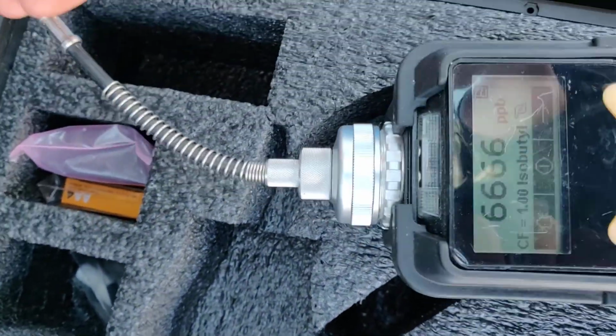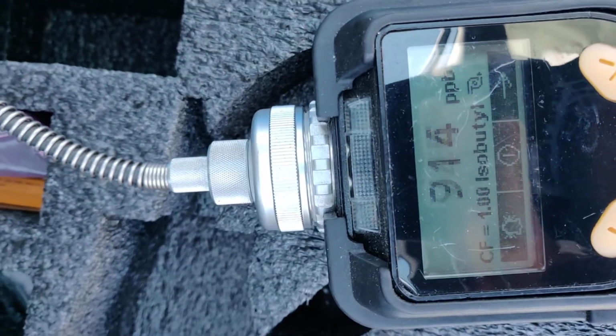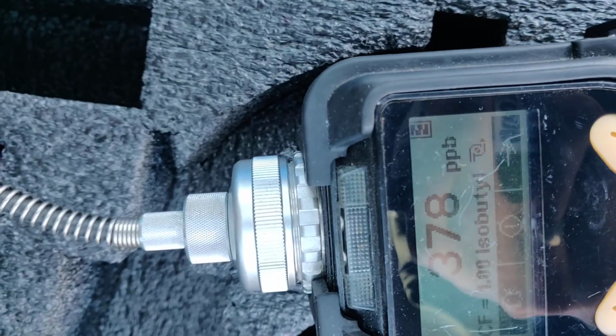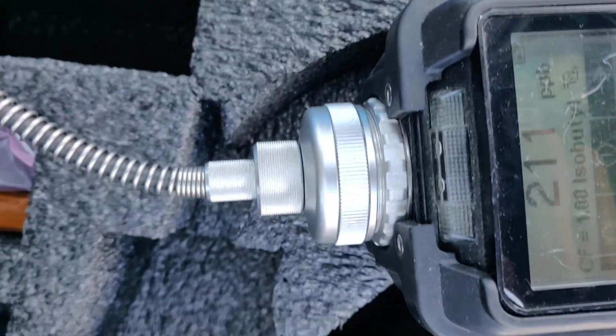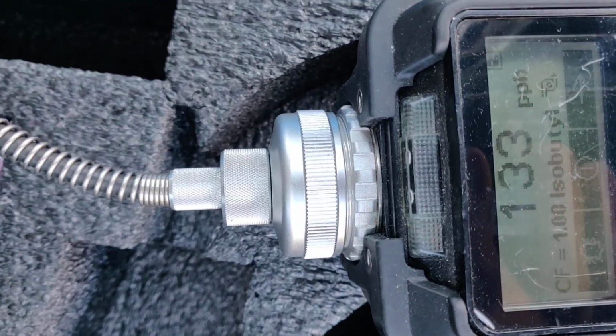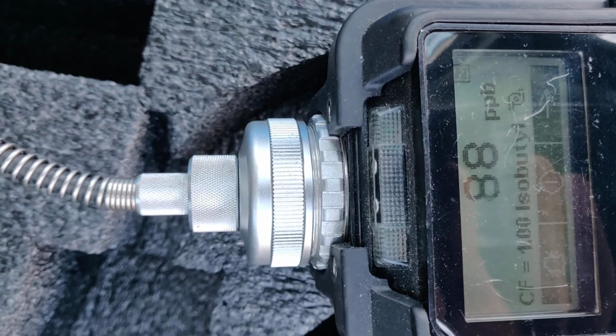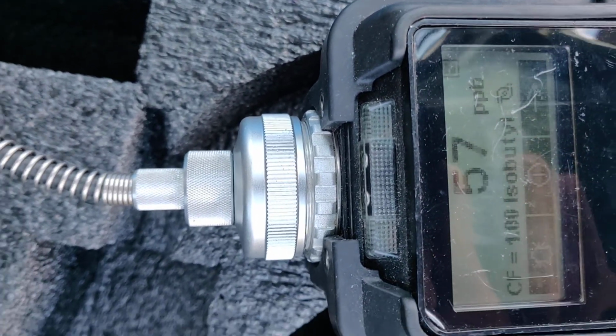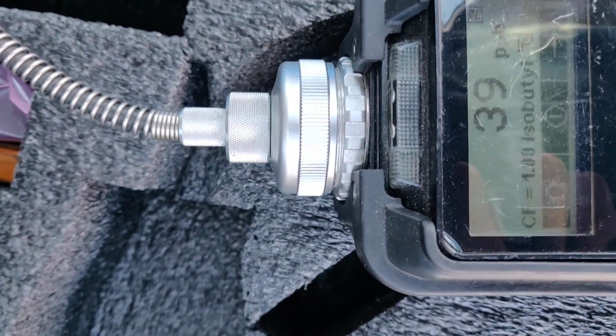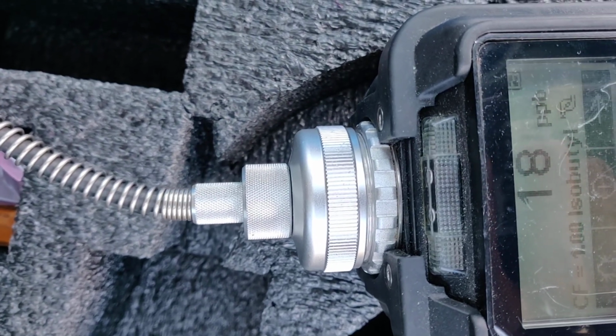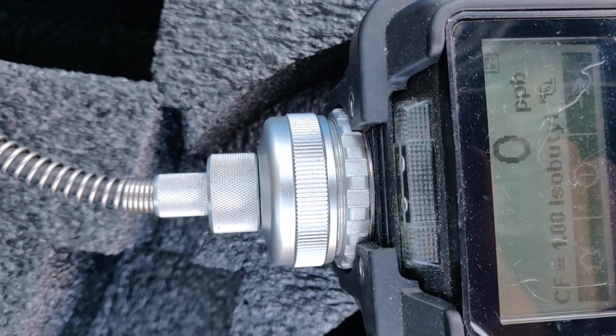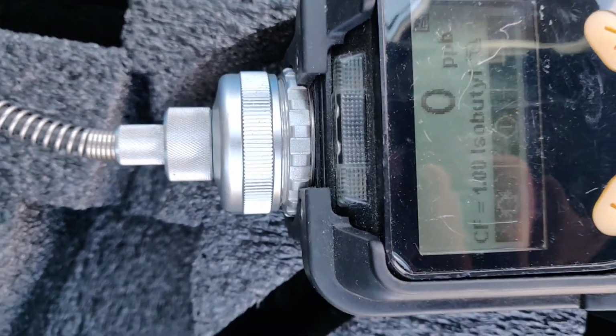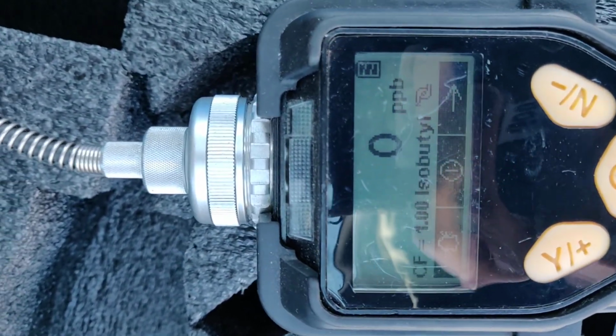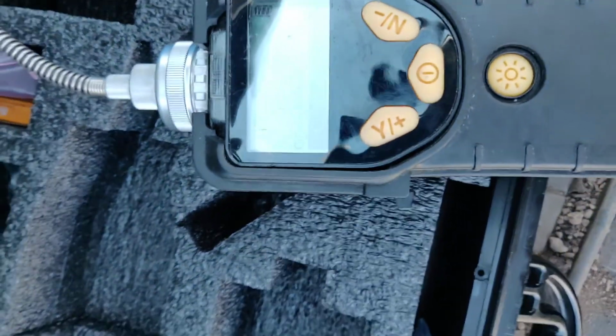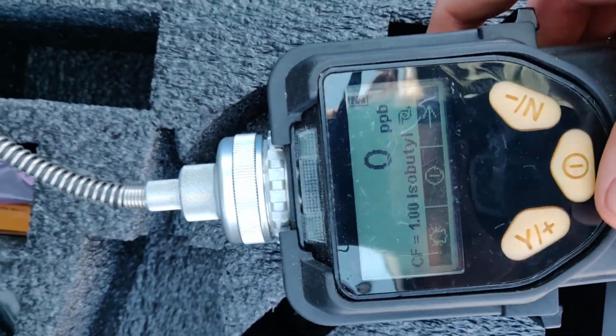Like I said, the lamp emits a steady energy pulse of ultraviolet light, which will ionize volatile organic compounds. The ionization energy will not destroy the volatiles, but it'll make the electrons from the outer molecular loop or whatever jump off, and these will be measured by the sensor inside. It measures the electrical, I think, current produced, and the current is what it measures, which translates to PPB. And since we used our zero filter, we can be sure that this is truly zero. So there's no VOCs in my car. That was the calibration process.